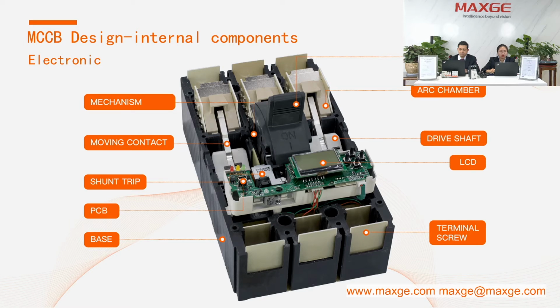Now let's see some internal components of our MCCB. First of all, in the PPT we can see the mechanism here. Then here we have a unique design of two moving contacts. Normally, competitors only use one moving contact, but we use two moving contacts to control the temperature rise. And we have the shunt trip mounted here. There is a PCB mounted here.